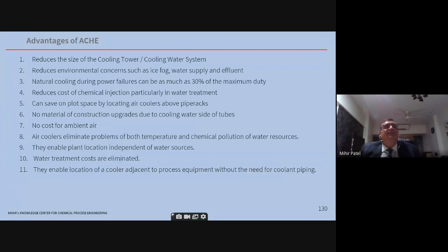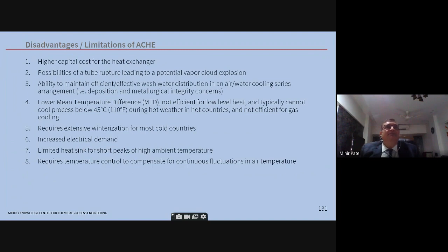Now, these are the various advantages as I mentioned. Point number 5, you see, can save on plot area space by locating them on the pipe rack. Then only the OPEX is involved. You are saving on water resources, and it saves on the cooling water system totally if you go with air cooled. But the disadvantages are higher CAPEX. OPEX cost also comes into play because of the operating power of the motors. In a tube rupture case, you can have a lot of hazard there, unlike a shell and tube. And winterization, you have to be careful here. In winterization, you don't want icing on the tubes. So in winter, in cold countries, the hot air is recycled back to the suction in certain proportion so that you don't have icing on the tubes.